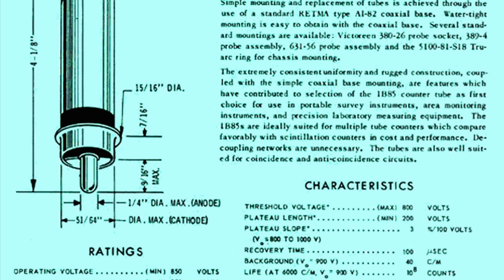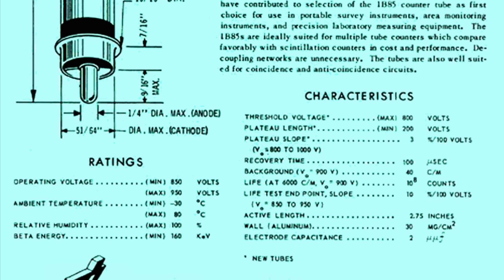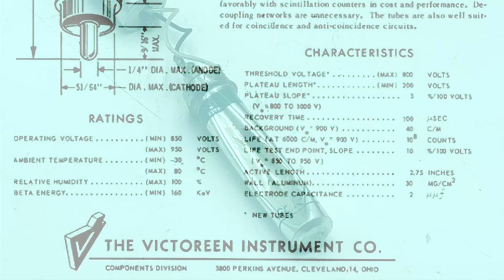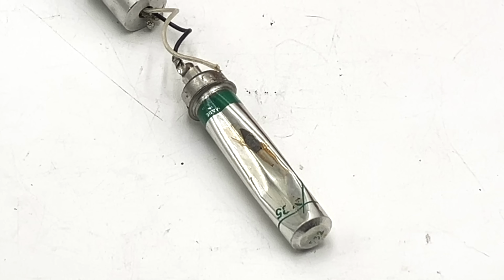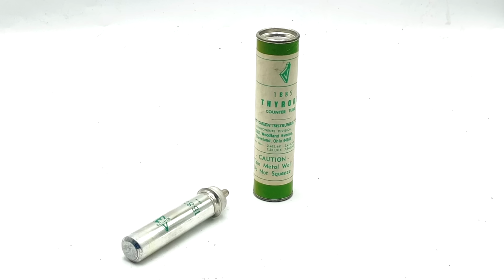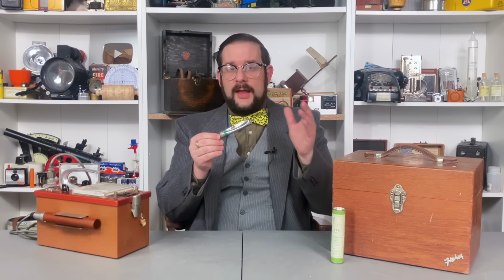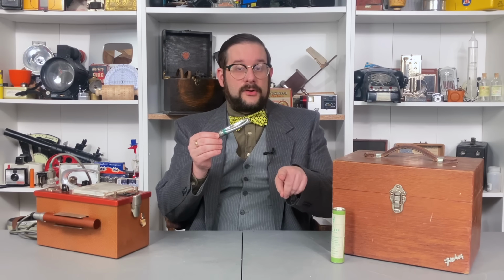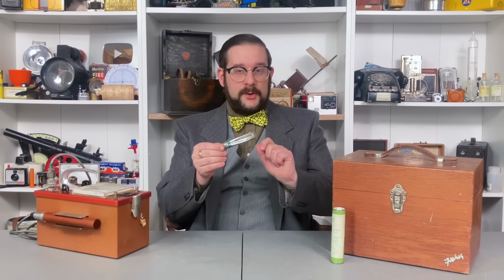You can dent the tube wall as much as 1/4 of an inch and still obtain satisfactory operation. However, most still tended to collapse like this one after sufficient use. Thankfully, I was able to get my hands on an intact example and swap it in. The 1B85 is made of aluminum and uses a detection gas mixture of argon with an organic quench gas, probably ethanol. It can detect both gamma and beta radiation, but not alpha particles, since they cannot penetrate the aluminum walls.